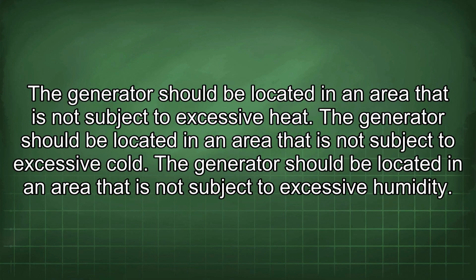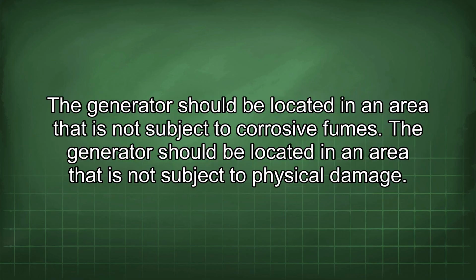The generator should be located in an area that is not subject to excessive heat, excessive cold, or excessive humidity. The generator should be located in an area that is not subject to corrosive fumes. The generator should be located in an area that is not subject to physical damage.